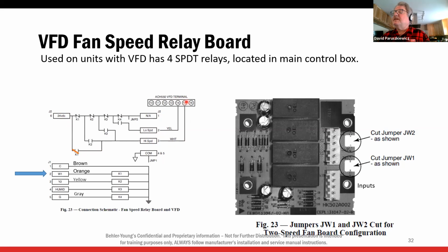This is the high speed relay. We energize the high speed at the VFD. So there you see it. That energizes, this closes, we send power to the VFD. Terminal 15 tells the VFD to go to high speed. Okay. Now these are relays.